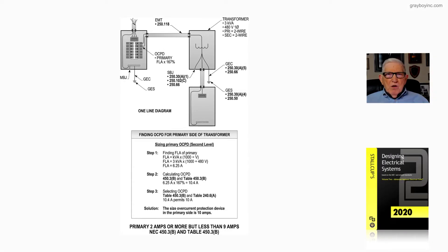Now we're going to size the primary overcurrent device with a full load current as less than 9 amps, but 2 amps or more, as outlined in our table 450.3B in the NEC.